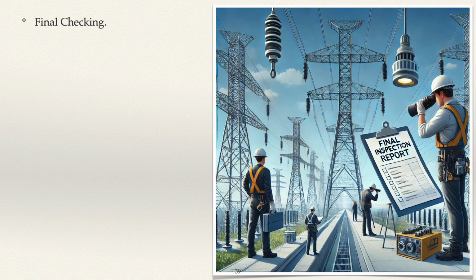H. Final checking. The purpose is to ensure that all site works are completed to specifications and that the site is prepared for handover. The inspection focus mainly on 1. Site clearing, verifying that the site is cleaned of all construction debris, materials, and equipment. 2. Ground clearance, ensuring that the minimum ground clearance for conductors is met as per safety standards. 3. Tower and conductor accessories fixing, conducting a final inspection of all installed components, insulators, dampers, conductors, earth wires, to ensure everything is securely in place and functioning correctly.